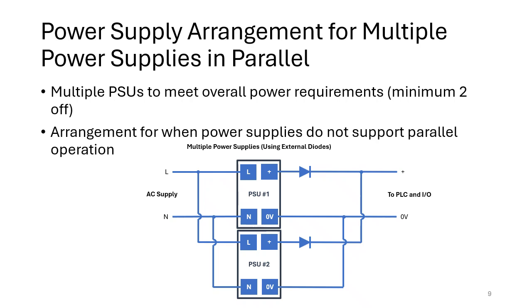So typically with a silicon diode, there's a 0.7 volt drop, which might not be relevant, might not be an issue. But if you've got a 24 volt power supply, you're now running at 23.3 volts because of a 0.7 volt drop. And if there are further volt drops due to terminations and so on, that means that your final voltage at your device could be lower than you really need it to be.